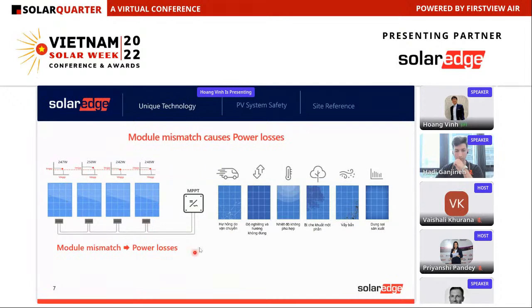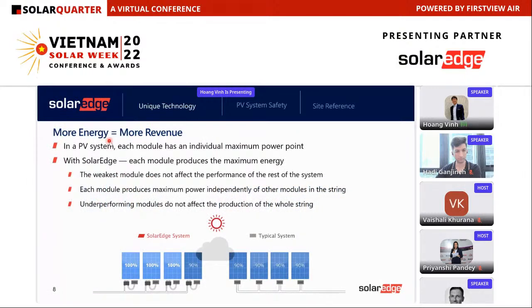So we can see here the red dashed line goes more and more down because of some trouble in the PV. You can see the maximum of the PV here is 250, but they cannot produce at the maximum power they can produce. They follow the lowest PV in the string, meaning this PV had low energy loss based on their ability, and time by time the dashed line becomes lower, the difference between the PV modules becomes more and more, meaning more energy loss, meaning more revenue loss.